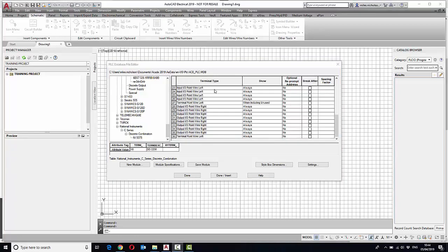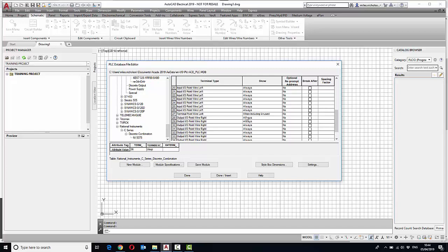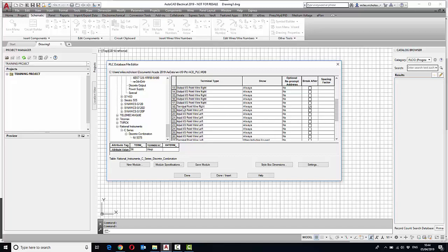So we've now defined all the connections, including the unused at the end. You can see on the connection which is not connected, we've put 'show when including unused only' and also have put an automatic break after the terminal point wire right. So in other words, after the first combined 16 inputs and outputs, just to separate them, have one on one sheet and one on the other.